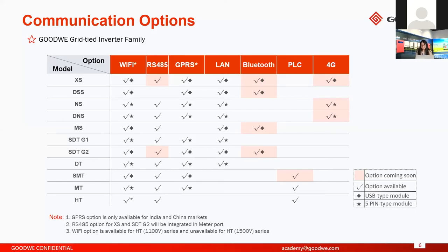PLC is actually used in larger projects, where you have a PV plant and the energy of the plant is mainly fed into the grid, not for self consumption. If you want to use PLC communication, first you cannot have any node on the AC side of your PV plant. There should be no consumption from your PV system. So PLC is used in the SMT, MT, and HT series.